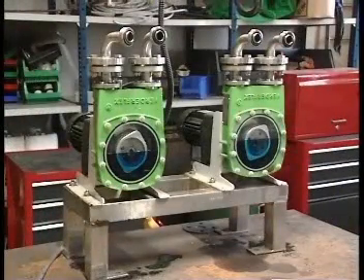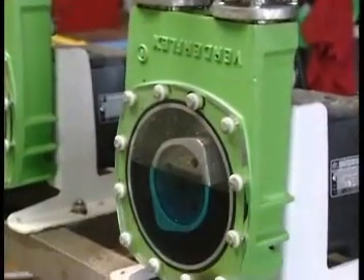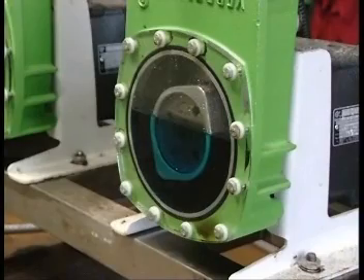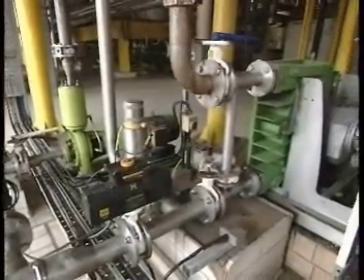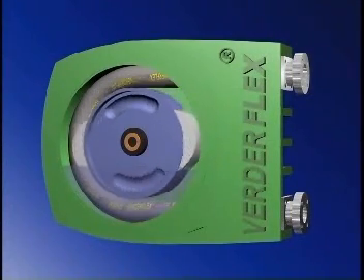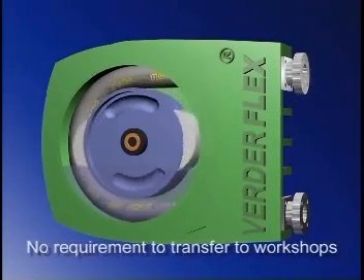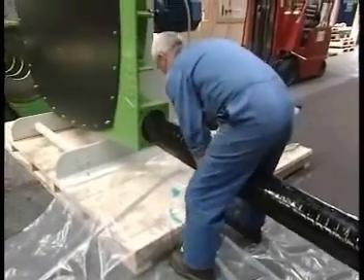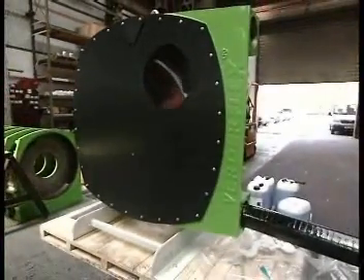Maintenance is another area where the Verderflex peristaltic pump scores above the competition. With no troublesome bearings or moving parts in contact with the product, reliable operational life is both extensive and predictable, reducing downtime to a minimum and allowing preventative maintenance schedules. A typical hose life of 2,000 hours can be achieved, depending upon specific process and duty requirements. There are no bearing alignment issues, and no requirement to transfer the pump to workshops for maintenance. In the Verderflex pump, the only sacrificial parts are the hose and the lubricant, and both are easily replaced on site with no special tools required.